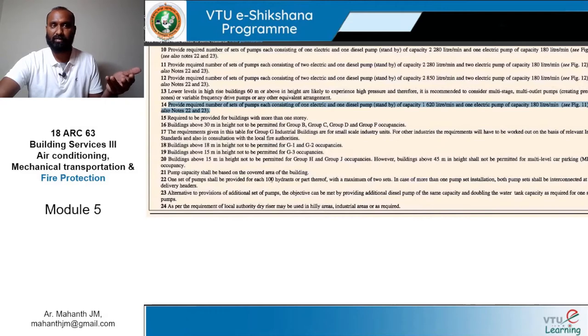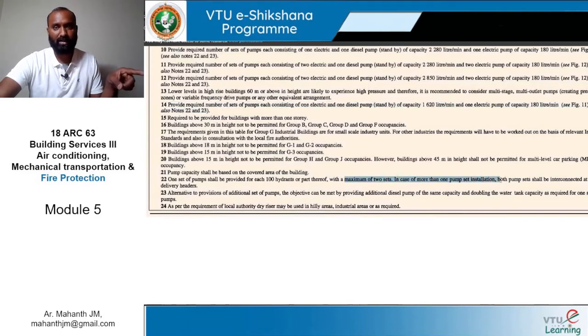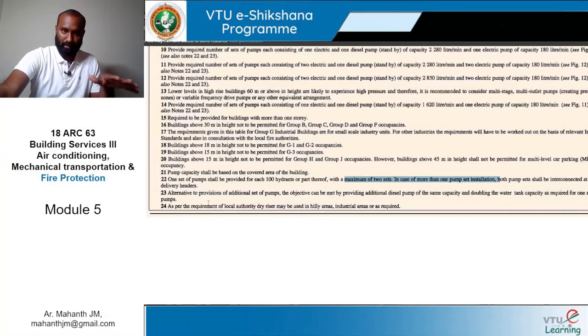One set of pumps shall be provided for each 100 hydrants or part thereof, with a maximum of 2 sets. In case of more than one pump set installation, both the pump sets shall be interconnected at the delivery headers. Alternative to provision of additional set of pumps, the objective can be met by providing additional diesel pump of the same capacity and doubling the water tank capacity as required for one set of pumps. Right? Maybe it's sounding a bit too much, but we are just referring to standards.